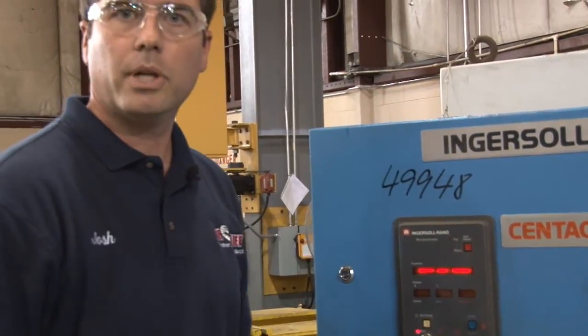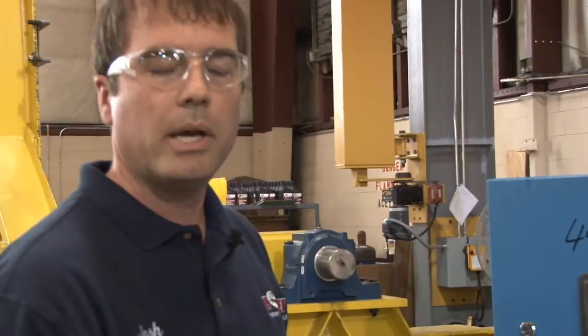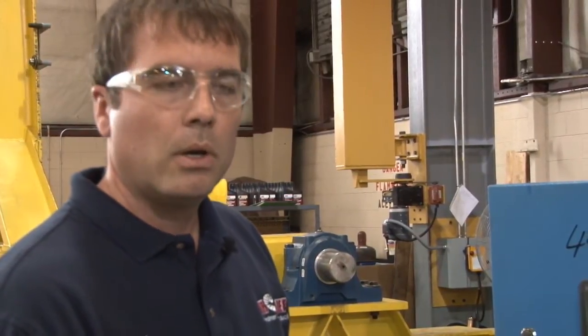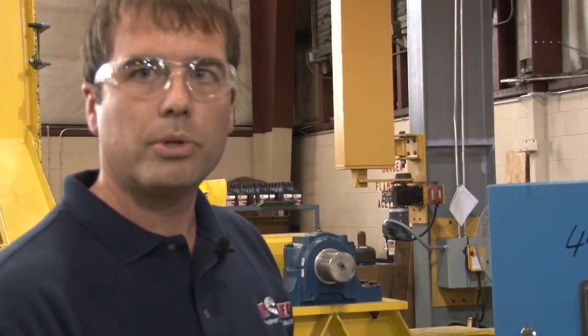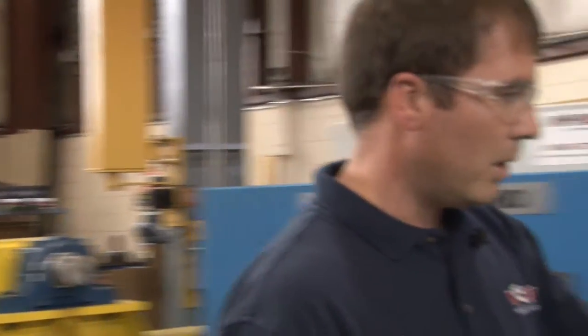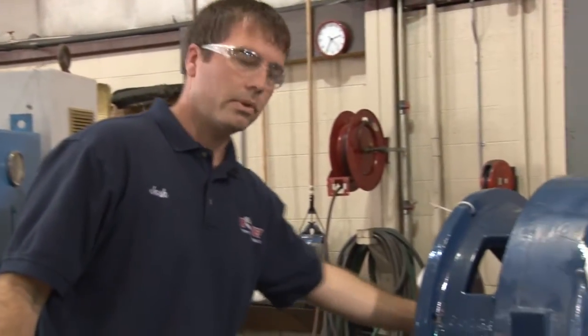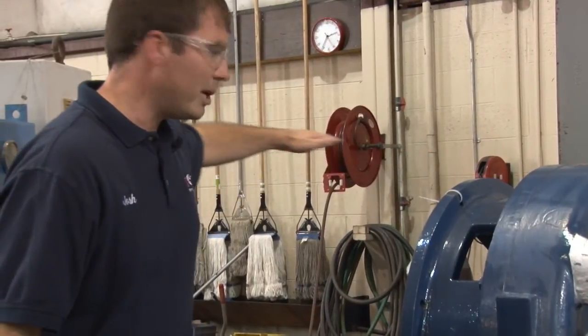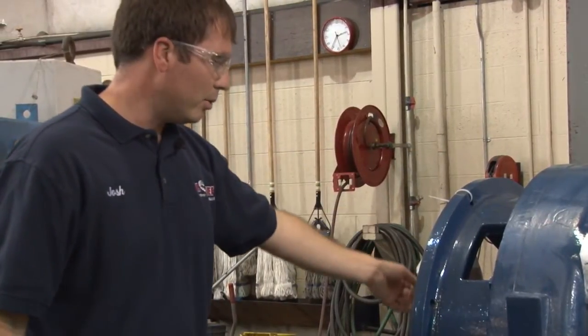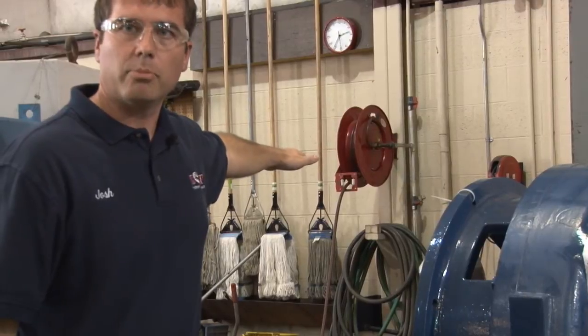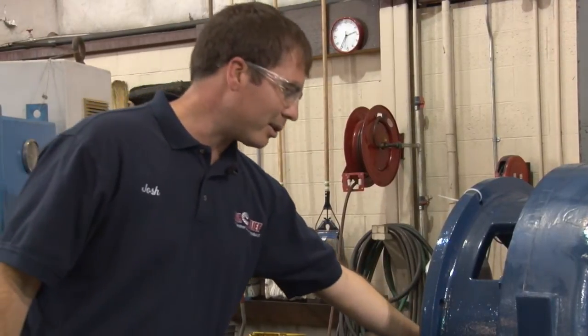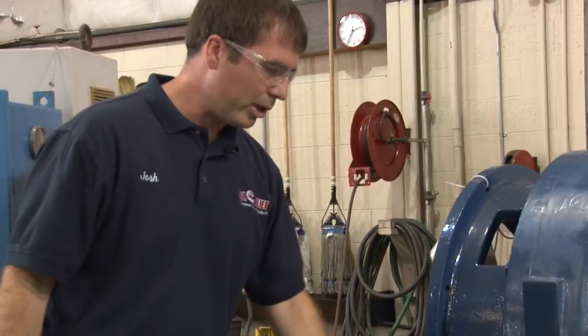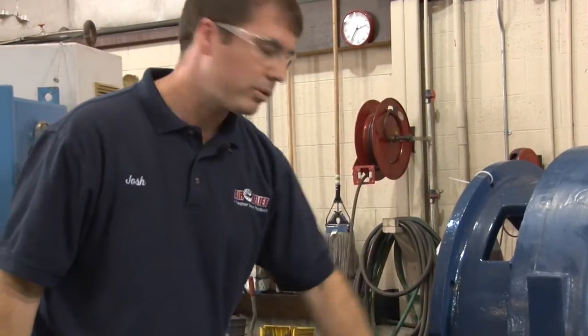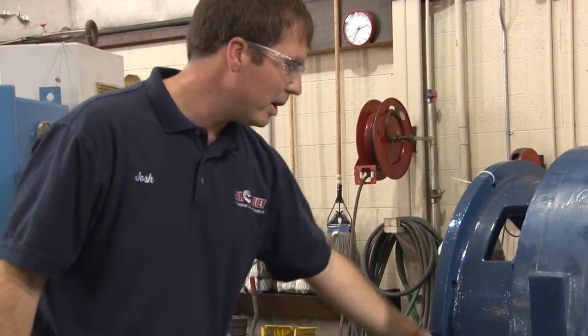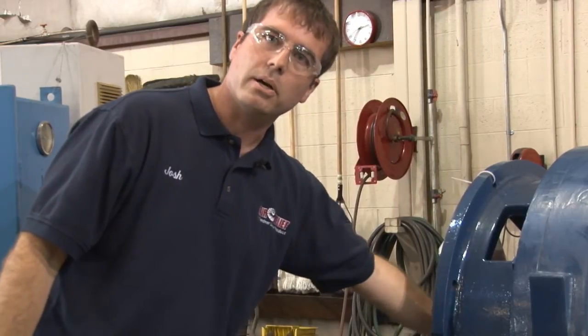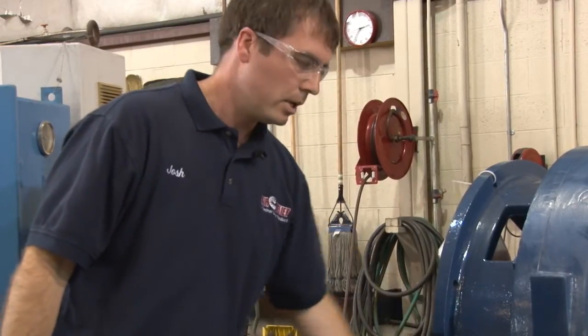Now, if you have known connections to be tight and clean and you still experience a problem, the next thing you can do is go to the compressor shaft, which would normally be here. The motor would be here on your machinery. You would disable the power to your motor, reach in and take the cover off, and you can actually leave the prelube pump on the compressor running, so you would have oil pressure at the bearings. Reach in by hand and spin the compressor shaft.